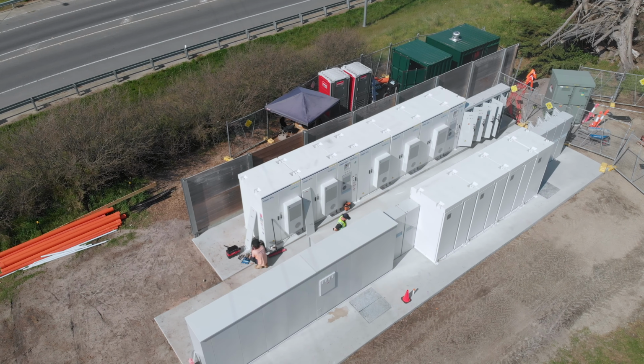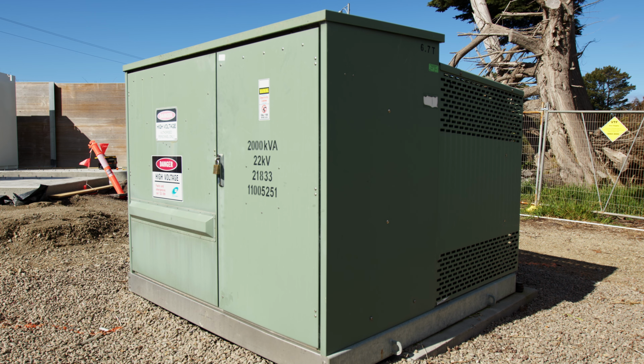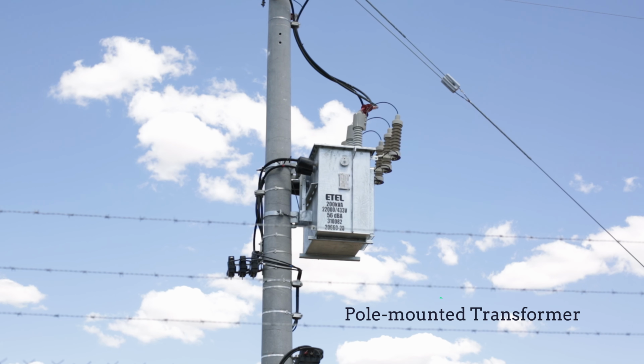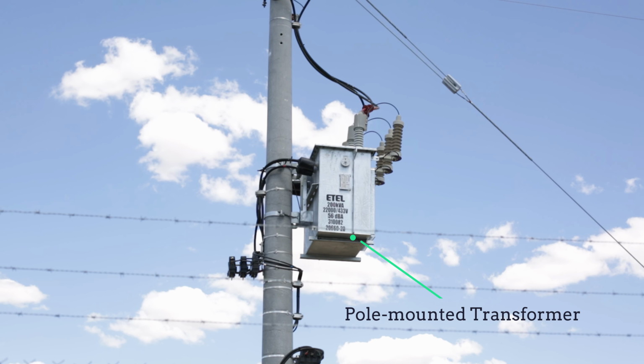So Alex, we were just talking about this transformer here, and just correct me if I'm wrong, is it dedicated for this particular site? It's not dedicated specifically for this battery site, but it is shared between Southern Plants and this battery. So what we're talking about is a pad-mounted transformer. A lot of the general public will be seeing transformers that are pole-mounted. But obviously, with the size of this transformer, 2 MVA, you're never going to stick it on a pole, are you? It's not possible. It has to be on a concrete slab.